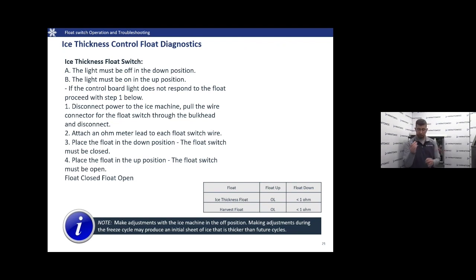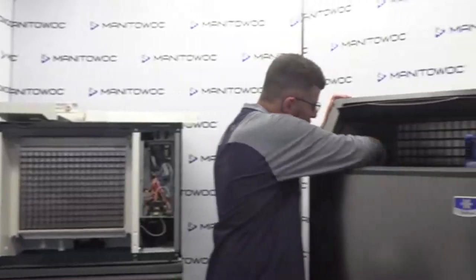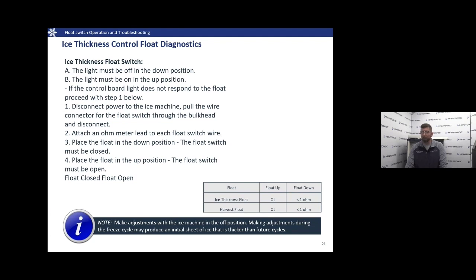Pull the connector through and you'll have access to your wires. Attach your meter leads to each float switch wire. Place the float in the down position — you should get a closed reading. Then move it up and you should get an open reading. Typically, when the float is up, you'd read open line or infinite; when the float is down, you'll typically read less than one ohm. Consistency is key — you want to see the same result each time. On the phones, you'll hear people tell you to do it 15, 20, 30 different times just to be sure you're seeing what you expect to see.